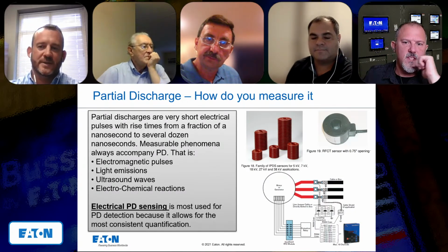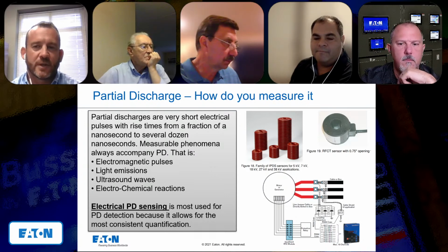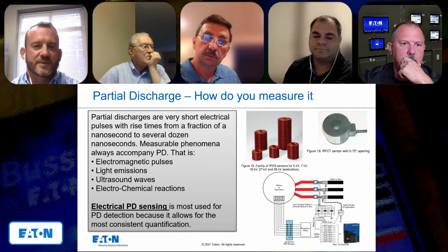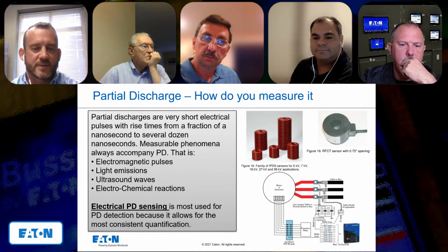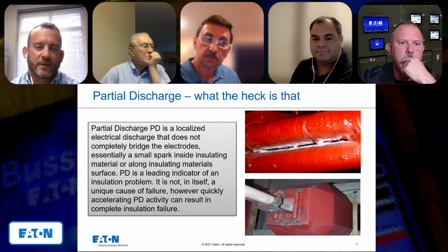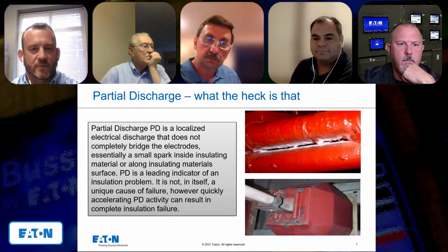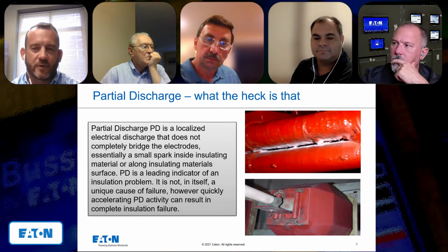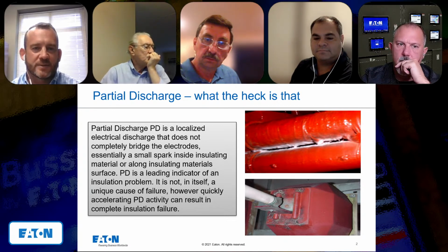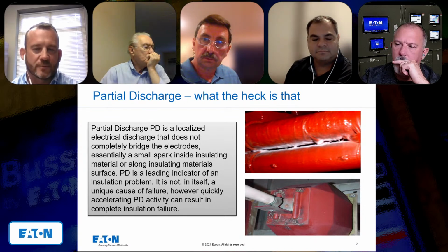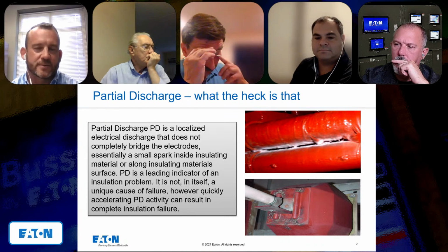Because if you look at these cases or these two pictures, typically you don't see these day to day. You only see these when you can take a shutdown. So if your shutdowns or maintenance intervals are a couple of years apart, one way of reducing that risk is to have the InsulGard relay, which is an active monitoring system.